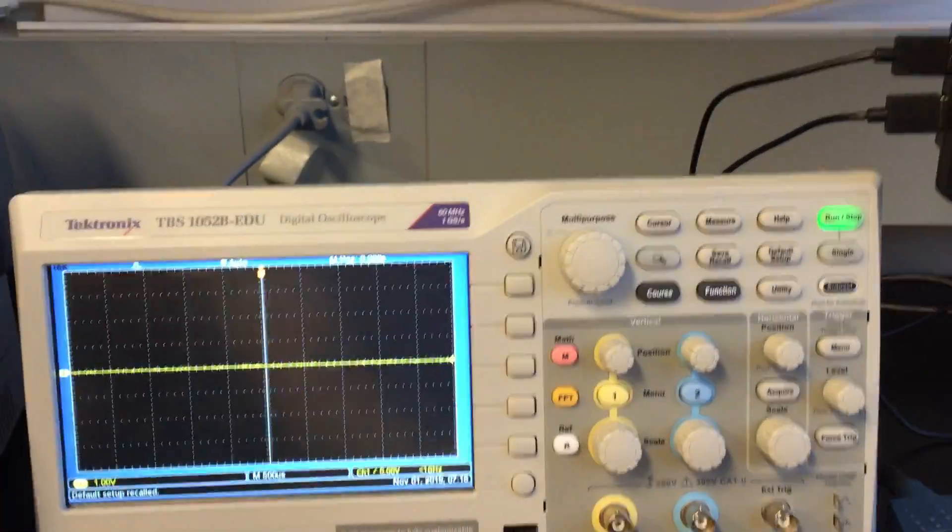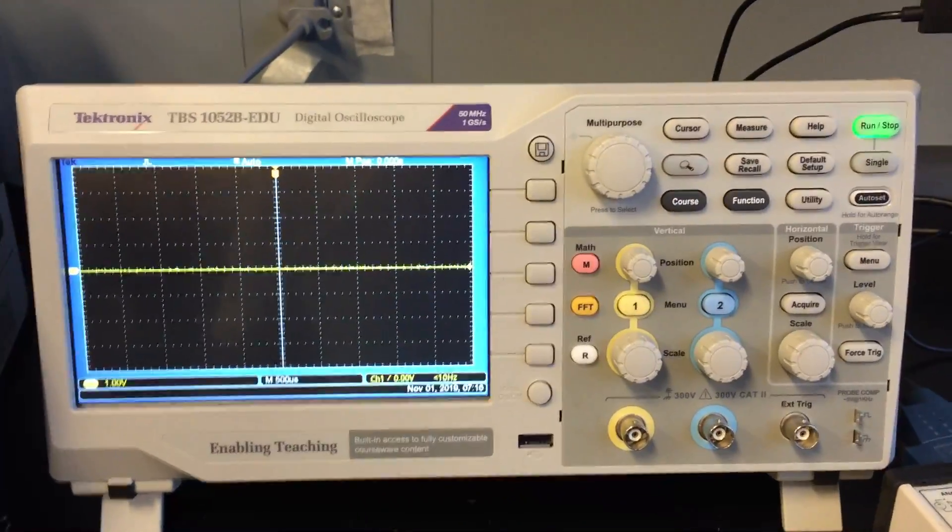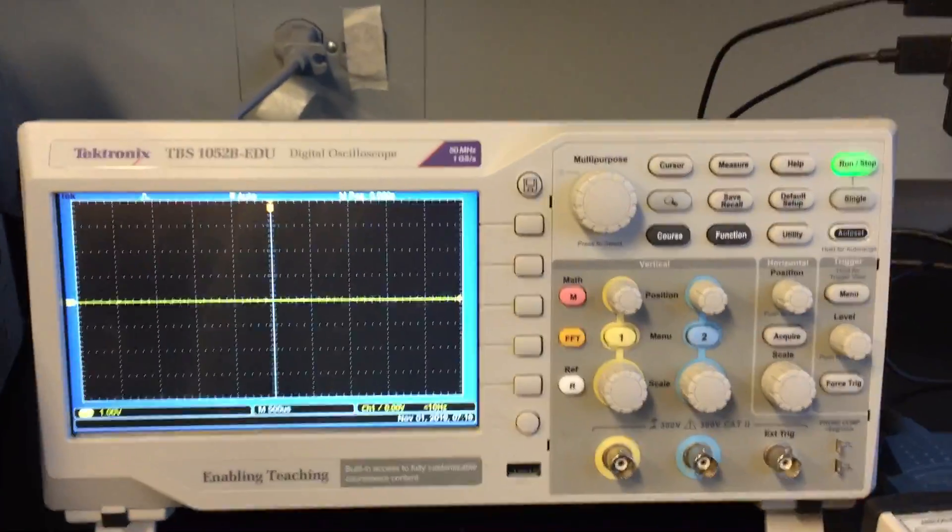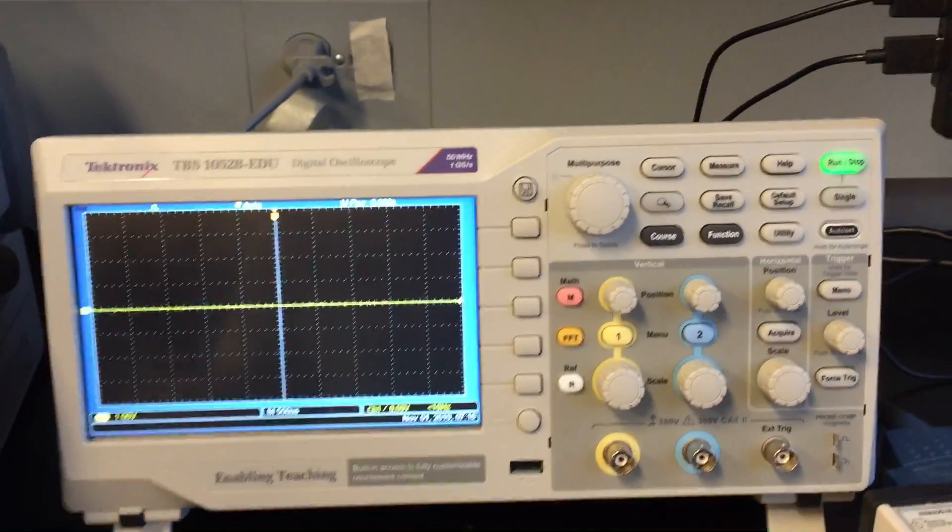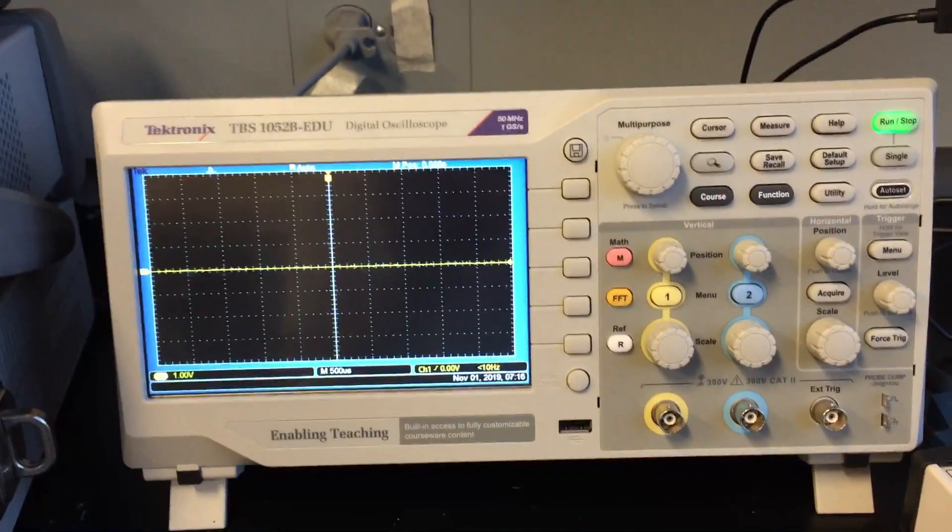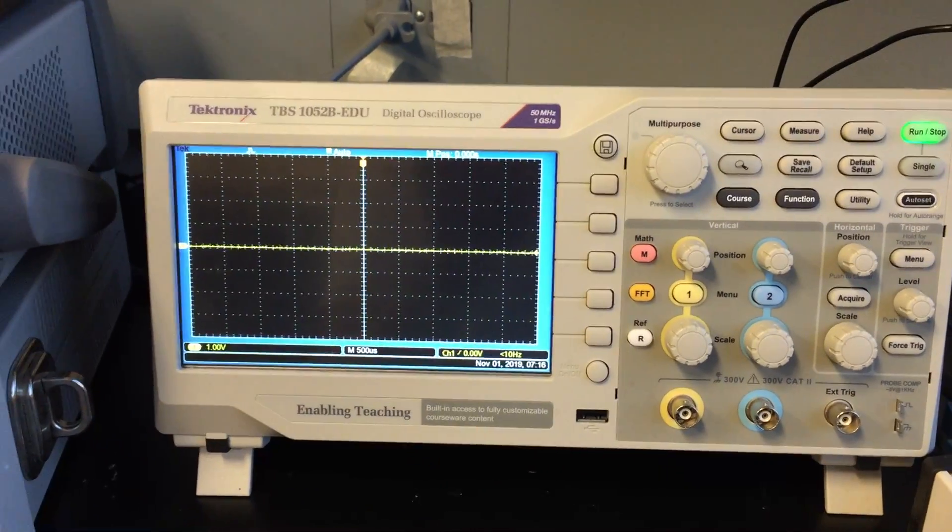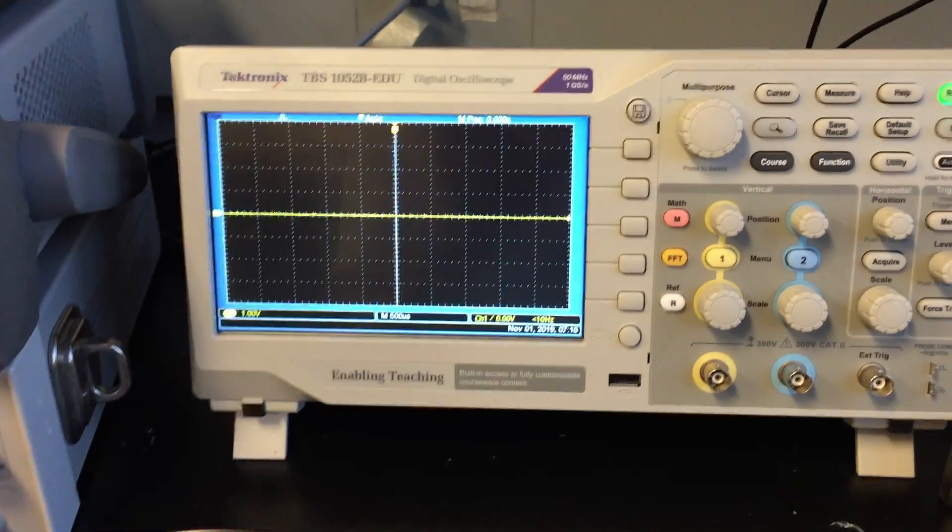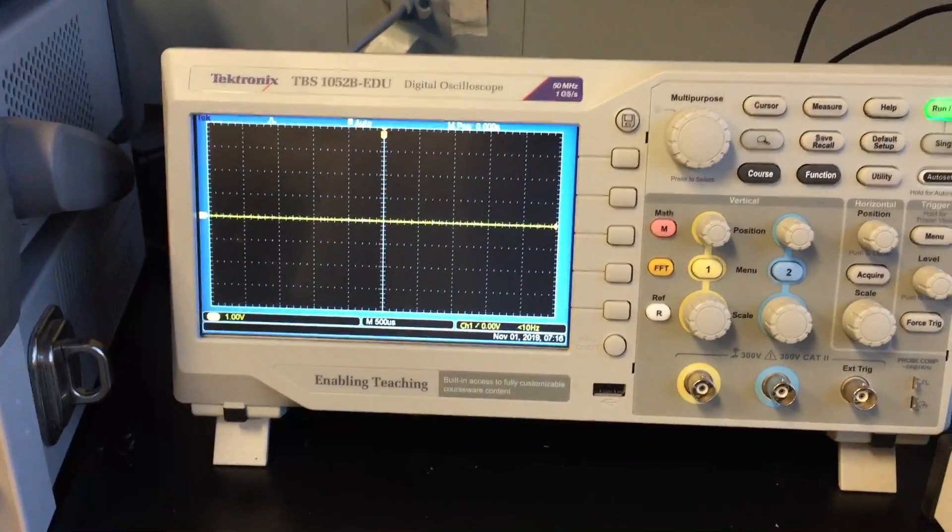And when you do that, that kind of ensures that no odd settings were made. You just don't know who was using it before for what. Maybe they have a weird trigger setup, maybe it's on nanoseconds or AC coupled. So if you bring it back to the default, it's very deterministic. Now, of course, then you have to know what the default settings are.